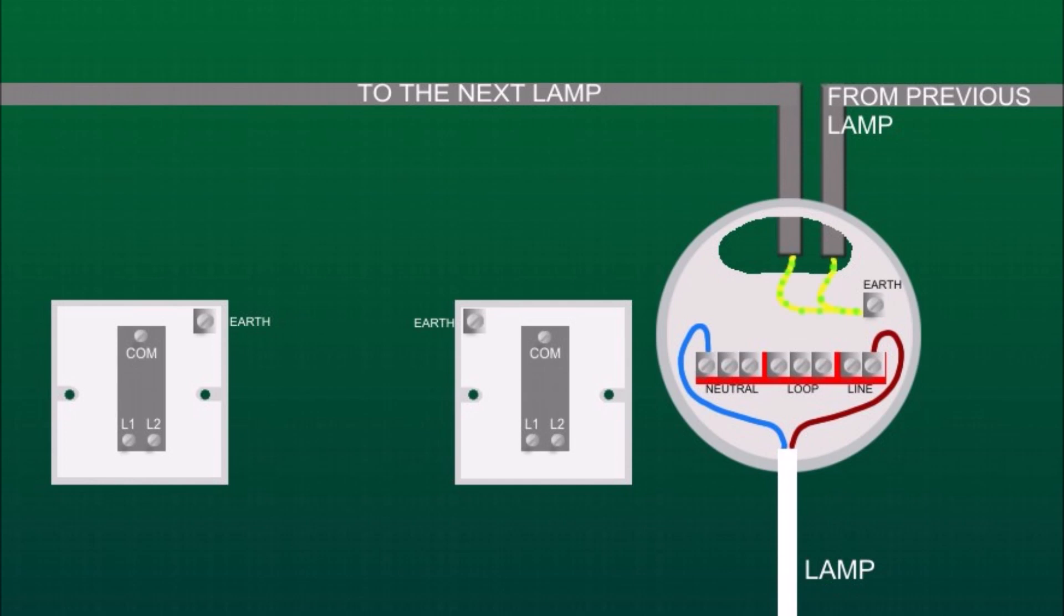So in this ceiling rose, both green and yellow earth wires from these two cables are connected to the earth terminal. Both blue neutral wires to neutral terminal, and both live brown wires to the loop terminal.